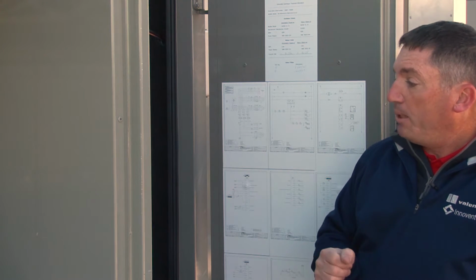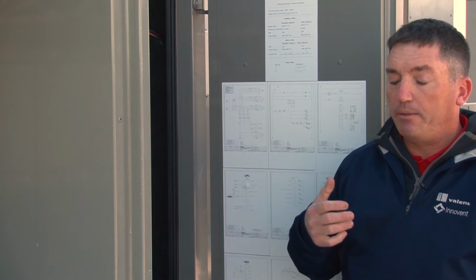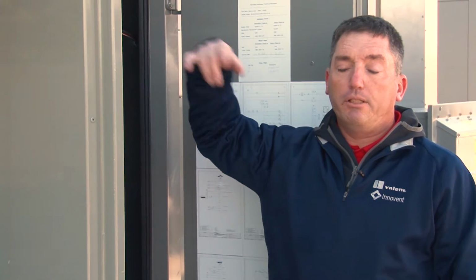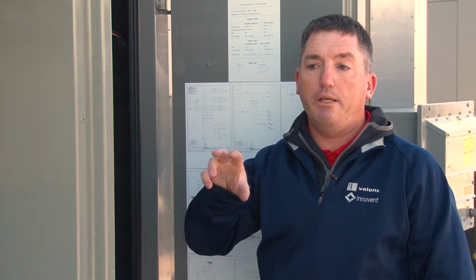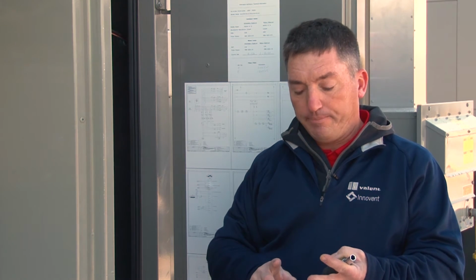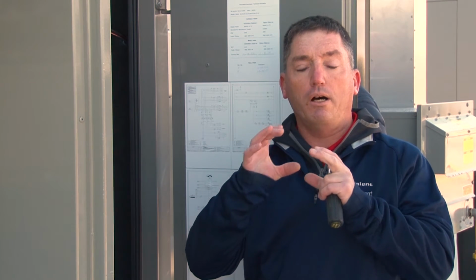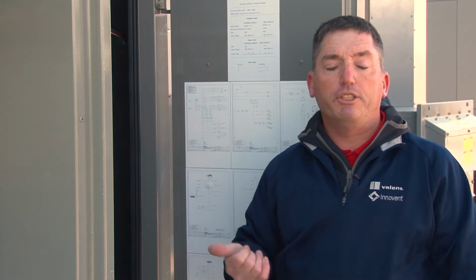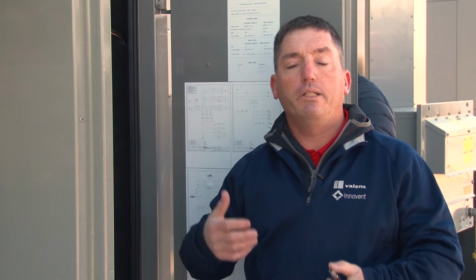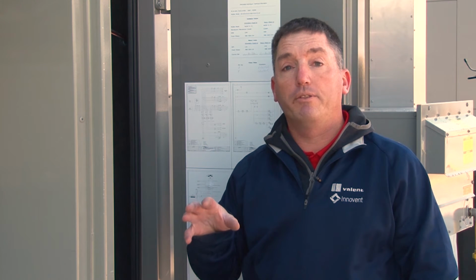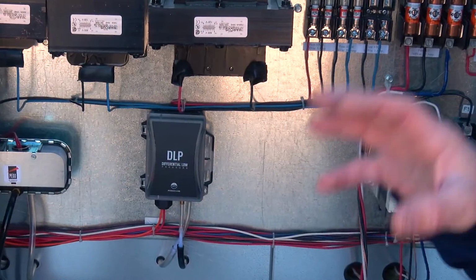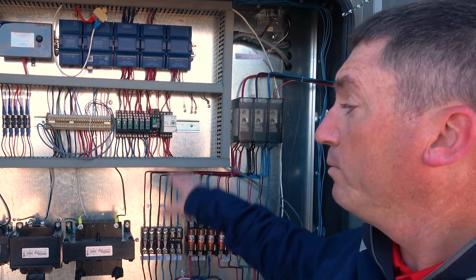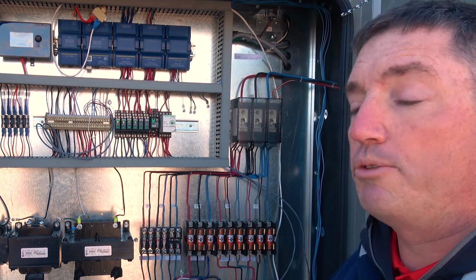Other than that, there's really not much else from an operator perspective. The PLC, and I'll cover this a little bit more downstairs on the user keypad. This unit, if it locks out on heating, if there's an issue with the furnace, or an issue with the cooling, an issue with the humidifier, an issue with the fans, you're actually going to get an error code on the keypad downstairs. Your first indication is most likely going to be that you notice the unit isn't supplying warm air or cool air to the space. Next thing to check would be that operator keypad, see if there is a local error there, and then from there you can come up here and start to investigate what the possible cause might be.